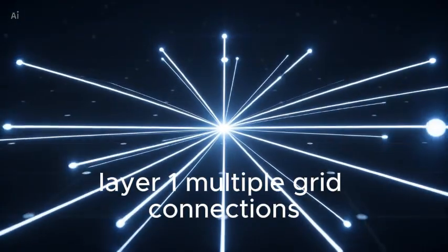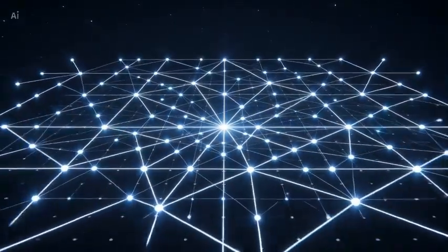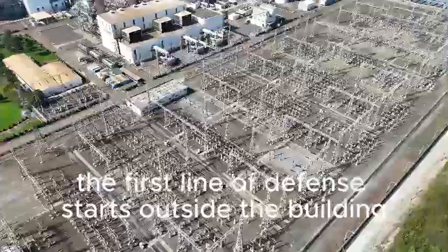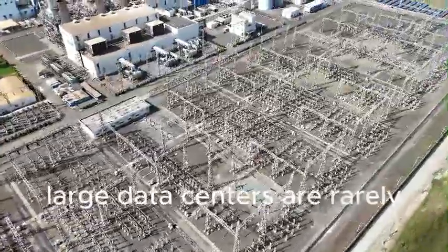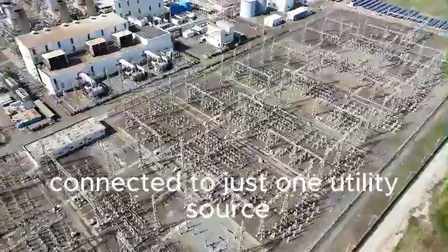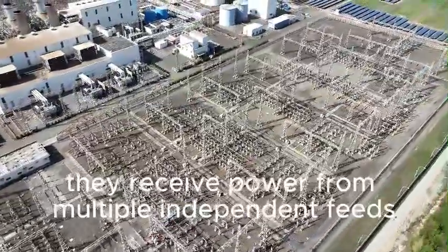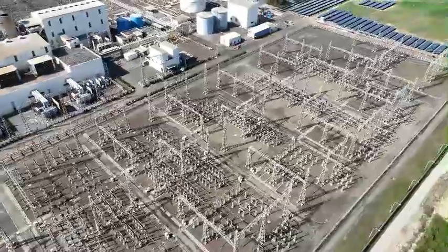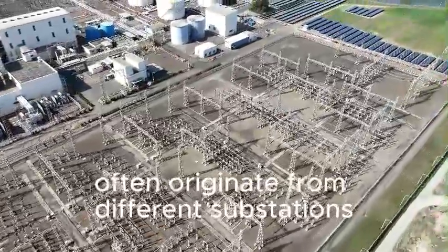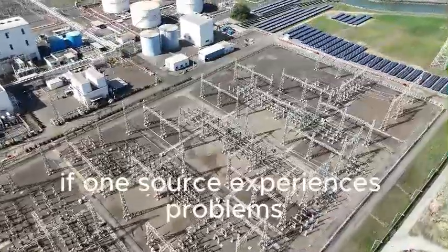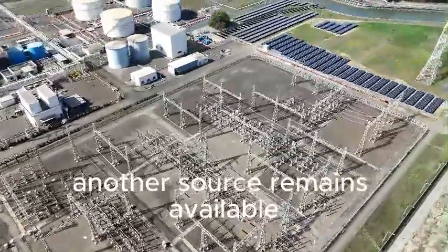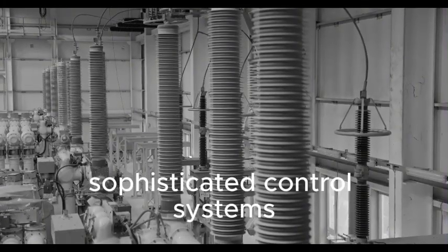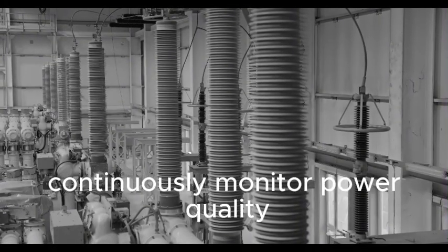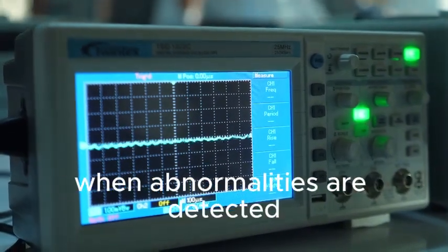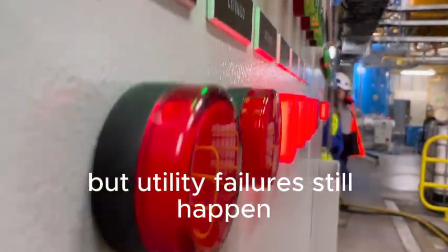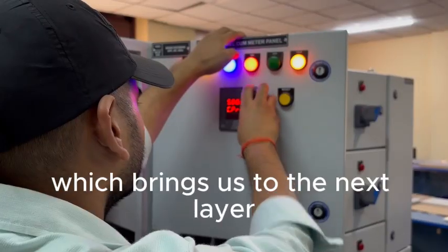Layer 1. Multiple grid connections. The first line of defense starts outside the building. Large data centers are rarely connected to just one utility source. Instead, they receive power from multiple independent feeds. These connections often originate from different substations and transmission lines. If one source experiences problems, another source remains available. Sophisticated control systems continuously monitor power quality and automatically transfer loads when abnormalities are detected. But utility failures still happen, which brings us to the next layer.